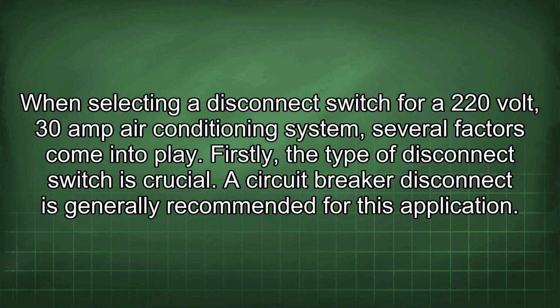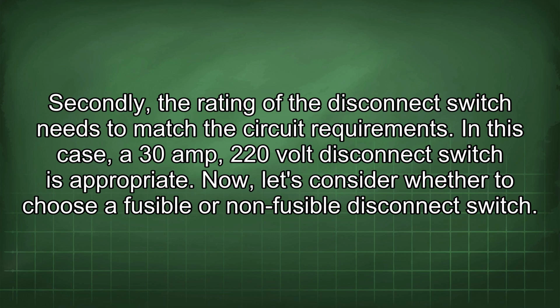When selecting a disconnect switch for a 220 volt, 30 amp air conditioning system, several factors come into play. Firstly, the type of disconnect switch is crucial. A circuit breaker disconnect is generally recommended for this application. Secondly, the rating of the disconnect switch needs to match the circuit requirements. In this case, a 30 amp 220 volt disconnect switch is appropriate.